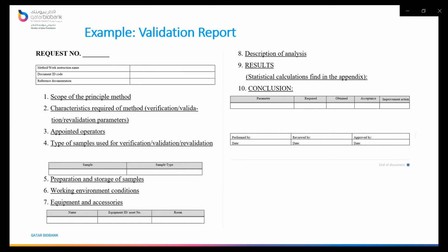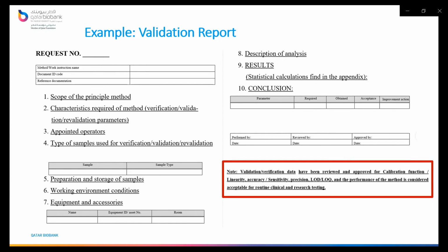And in the report, we have to take different things into consideration. So our scope, the characteristics of the required method, appointed operators, who should be trained and competent to perform this task and not introduce additional bias and variability into your method validation, types of samples, how we prepare them, how we store them, what the working environment conditions are, what kind of equipment and accessories we used, and of course the most important thing, the result analysis, followed by the conclusion, where we will put a comparative table: what we required, what we obtained, and what we are going to accept. As I said, a very important statement at the end of every validation report is that all these parameters were reviewed and approved, and they are ready for routine clinical and research testing.